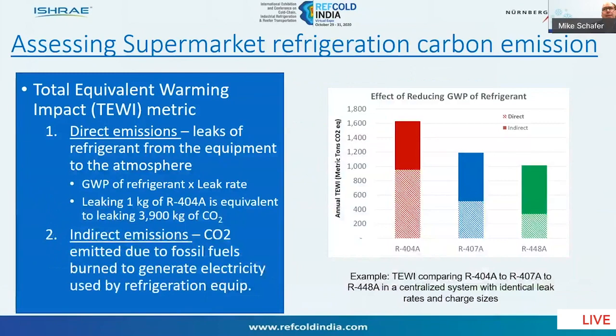So how do we assess the supermarket refrigeration carbon emission? One of the metrics that we look at is the total equivalent warming impact, which is a function of the direct emissions and the indirect emissions. So direct emissions are simply the leaks of the refrigerant from the equipment. And that would simply be the GWP of the refrigerant times the leak rate times the charge. So as an example, leaking 1 kilogram of 404A is equivalent to leaking 3,900 kilograms of CO2.